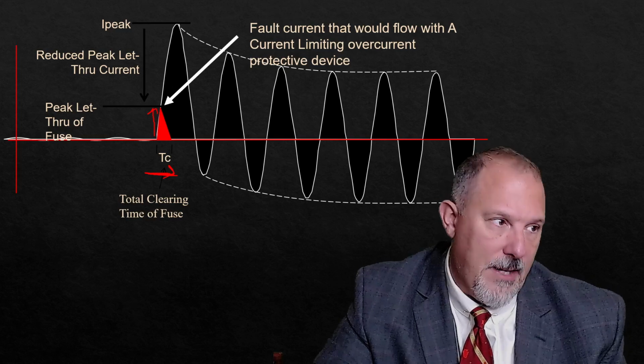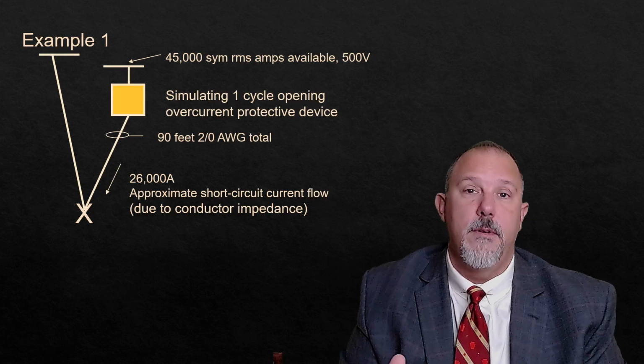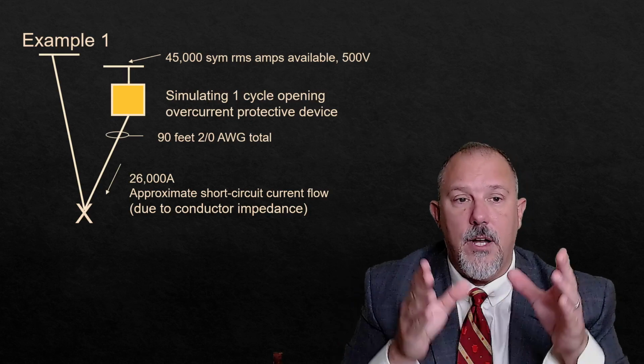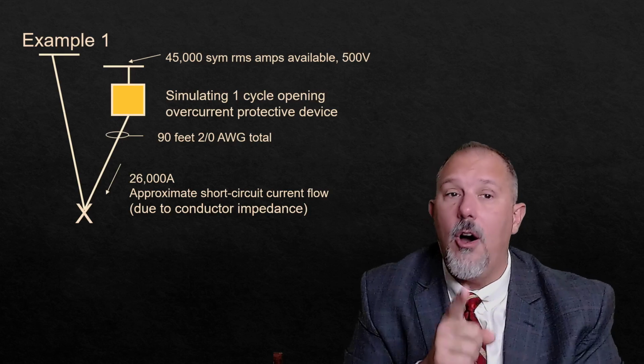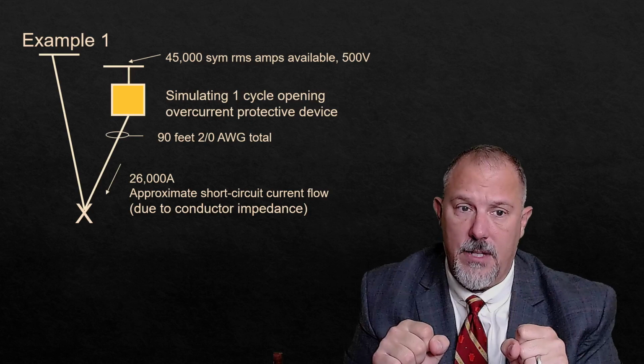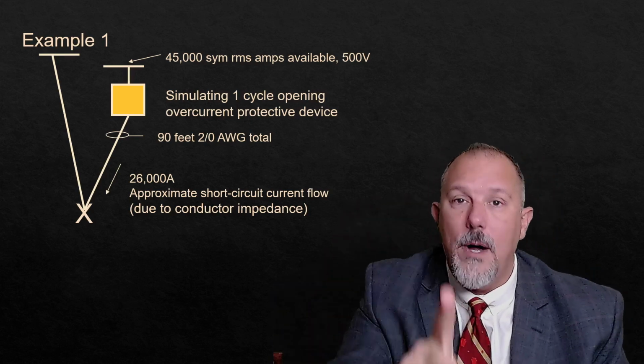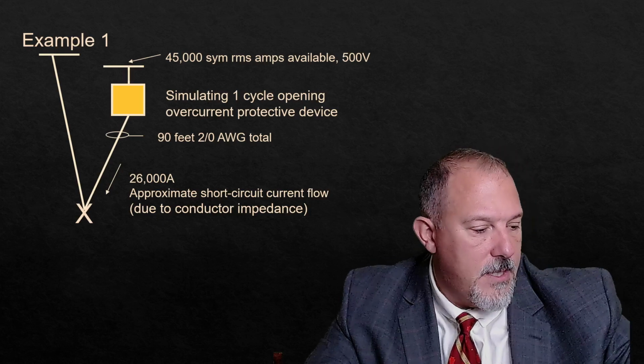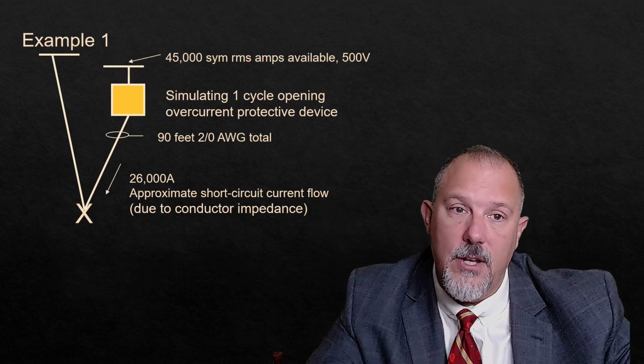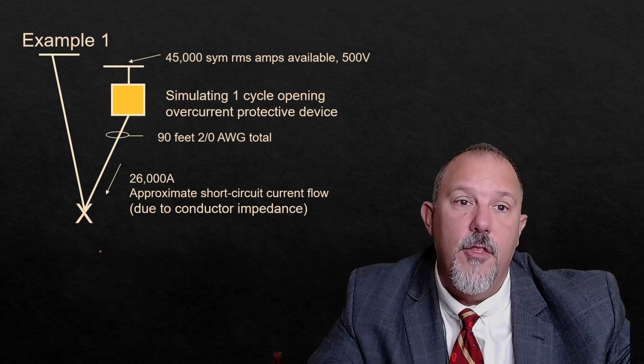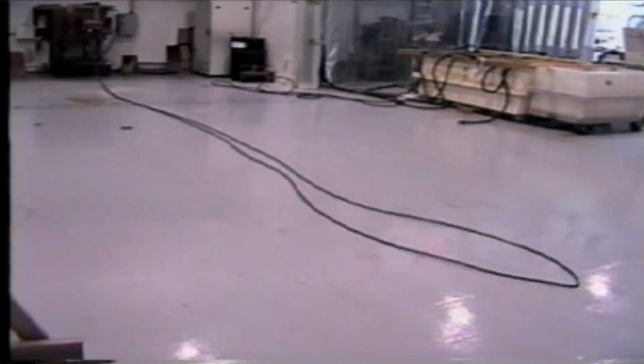And how we demonstrate this is through what we call the cable whip video. Here's what happens. We take a circuit. We take 90 feet of 2-aught conductor. You know how stiff 2-aught conductor is. We pass 26,000 amps through it for one cycle. This is the result of one cycle of 26,000 amps of bolted fault through a conductor. One cycle of current. All that was one cycle of current. That is a lot of magnetic force.